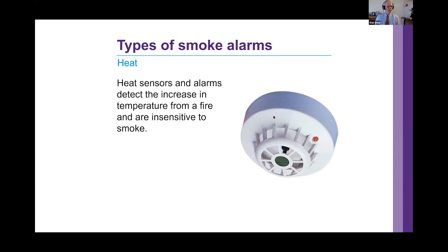Heat sensors and alarms, again as specified in the fire risk assessment. A thorough, suitable and sufficient fire risk assessment will look at the detector in place and make appropriate recommendations. Heat detection is very important, especially in a kitchen area, to avoid false alarms, and to be used in conjunction with ionizing detectors. The heat detector can be identified visually by what looks like a metal black spike coming down in the middle of a protective cage.